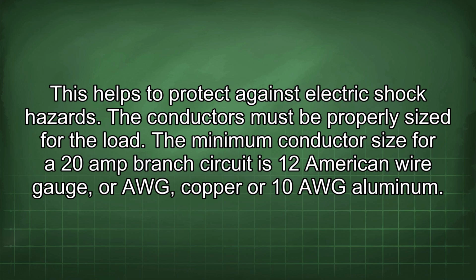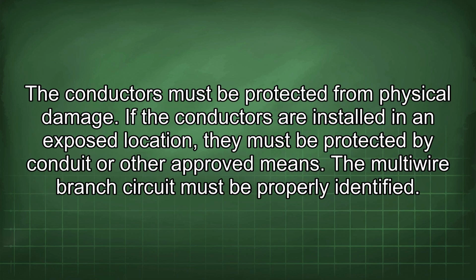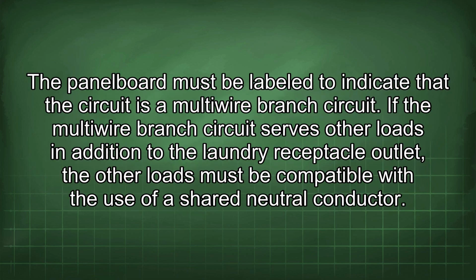The conductors must be properly sized for the load. The minimum conductor size for a 20-amp branch circuit is 12 American wire gauge, or AWG, copper or 10 AWG aluminum. The conductors must be protected from physical damage. If the conductors are installed in an exposed location, they must be protected by conduit or other approved means. The multiwire branch circuit must be properly identified. The panel board must be labeled to indicate that the circuit is a multiwire branch circuit.